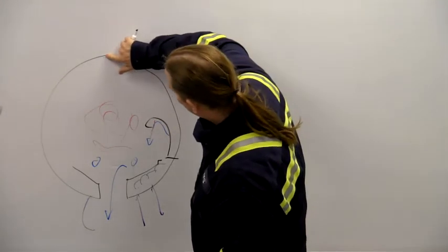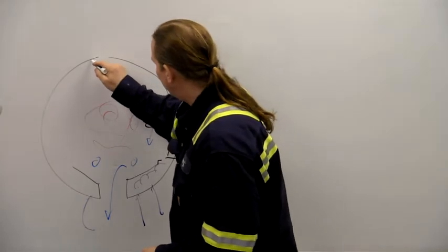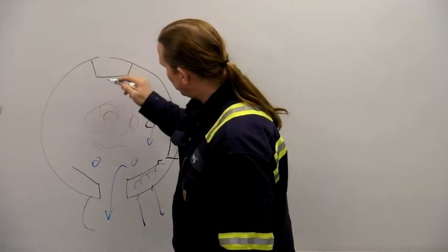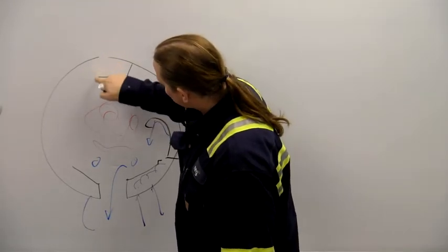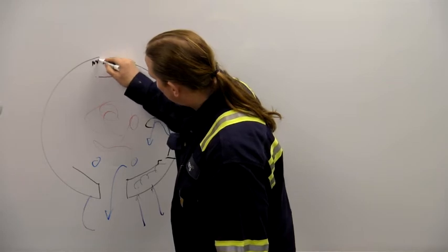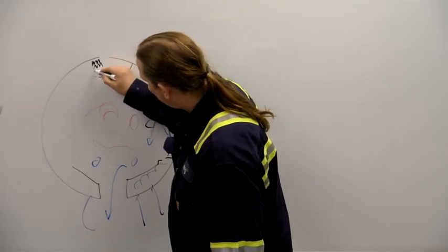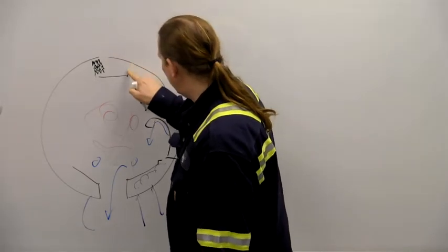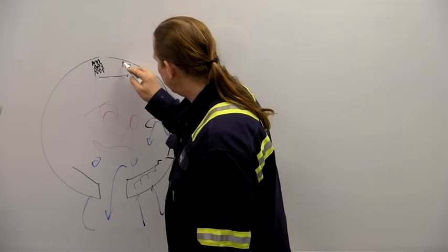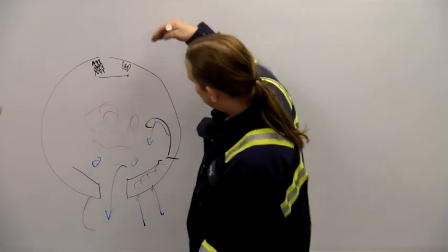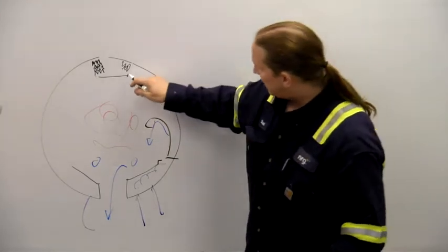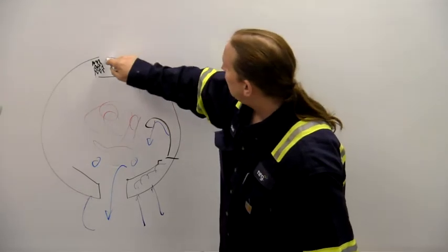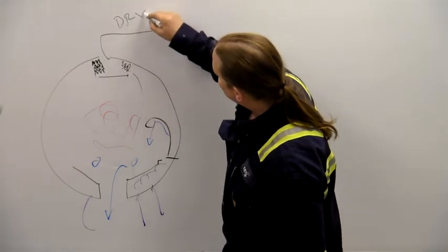So then, up at the top, there's chevron moisture separators. So the chevrons. Ooh, I made those too small. Chevron is French for zigzag. And as the steam tries to go through, the steam makes corners and the water doesn't. And so the water drips back down and makes another lap. And then what we have coming out the top is dry, saturated steam.